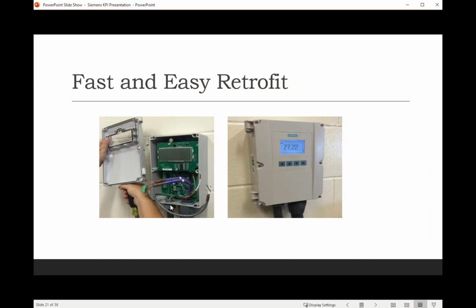One thing you need to remember though is that when you do switch out the older style Hydroranger for the new HMI, the serial number is not going to match up with the enclosure. So if you're calling in for a warranty purpose or to get a new one, remember that the serial number is on the board and not on the enclosure.